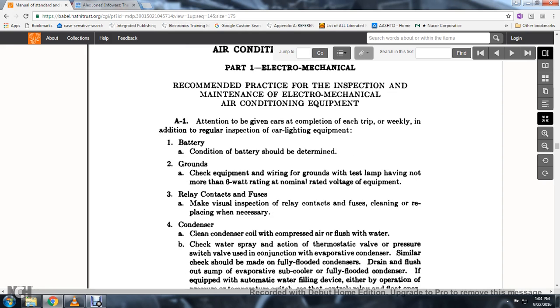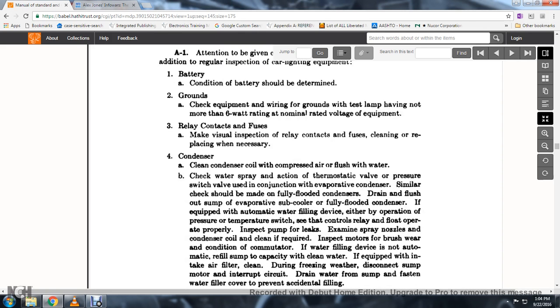4. A similar check should be made with the fully flooded condenser: drain and flush out the sump of the evaporative subcooler, and the fully flooded condenser. 5. If equipped with automatic water filling device, check the operation of the pressure or temperature switch, and see that control relays and the float operate properly.